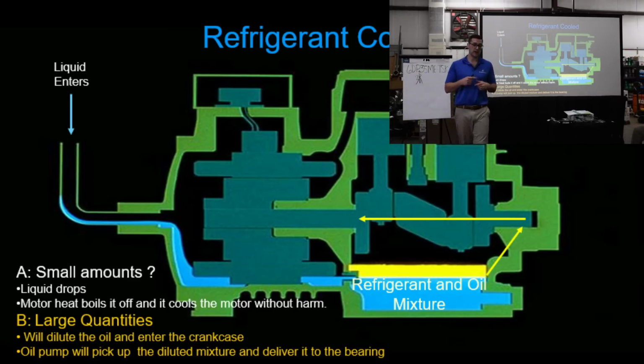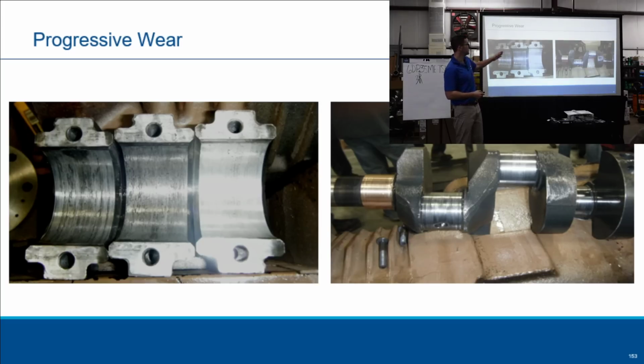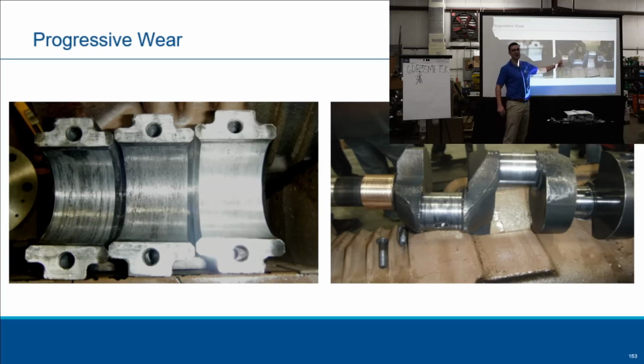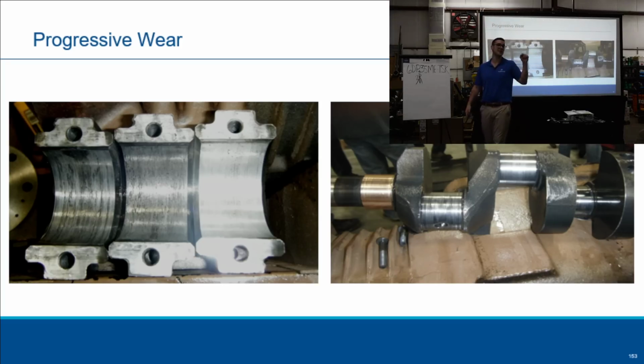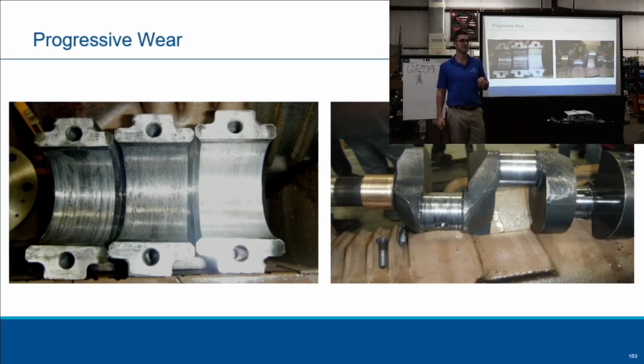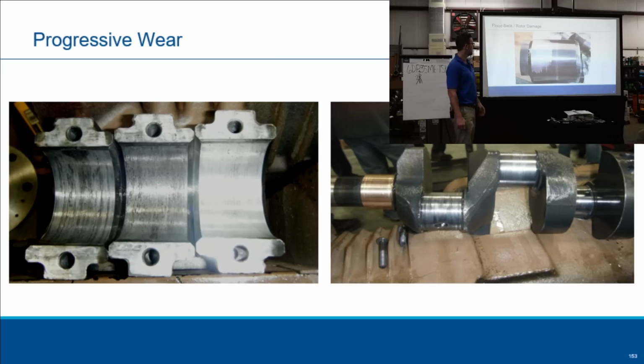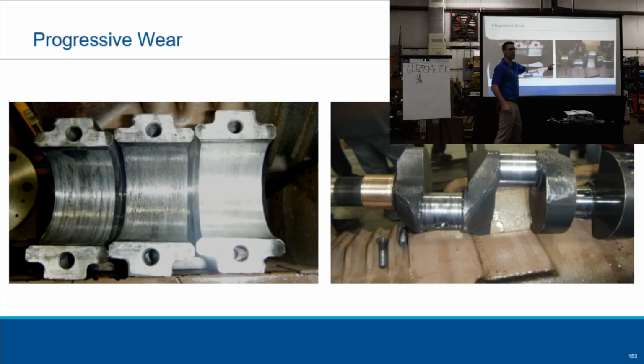So when that liquid refrigerant starts to get in there and start washing all that oil out, you're going to run into issues. And it leads to what type of compressor? A failed one, right? So progressive wear, what's this? What do you think this is right here? No. No, it's not. That's the bearing. The bearing shouldn't be on the crankshaft. It should be in the body. Okay? So I start to wear this bearing because of liquid dilution or liquid floodback.